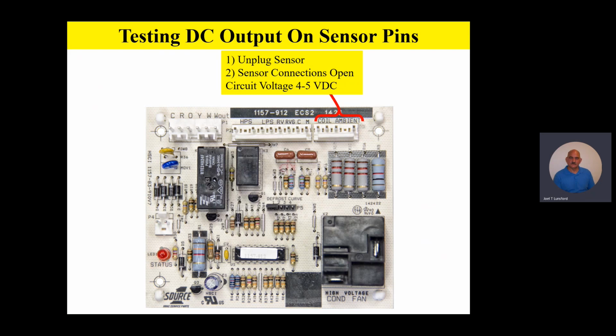So an example would be if I'm checking the coil sensor pins, I'll go between the two little coil sensor pins with my volt ohm meter, DC voltage, and I'm looking for 4 to 5 volt DC on the two coil pins. Then I'll go over to the ambient pins. You'll notice that they have a different spacing on them. That way you can't mix up the coil and the ambient, or the outdoor sensor, also called the ambient sensor, because the pin spacing is different. Same routine. If I go to the ambient sensor pins without the sensor plugged on, I should read 4 to 5 volt DC on the pins.